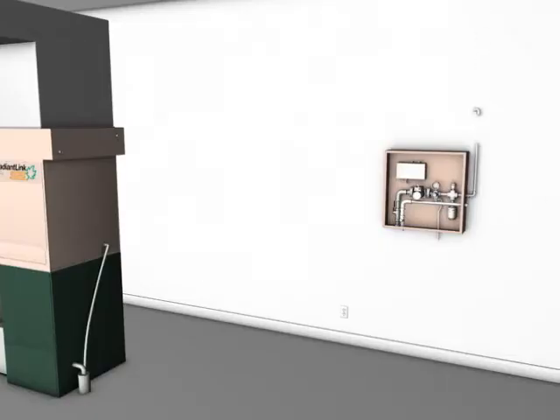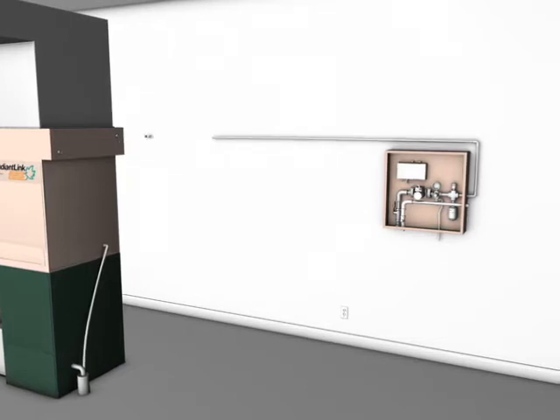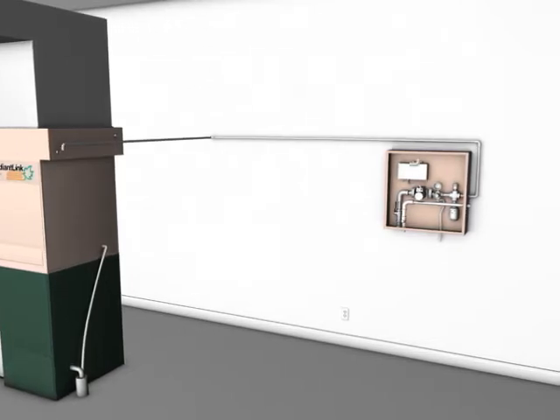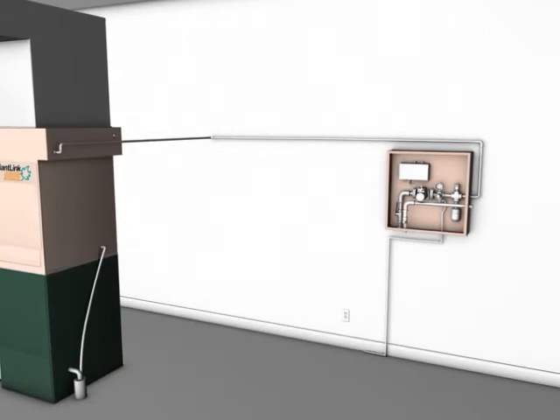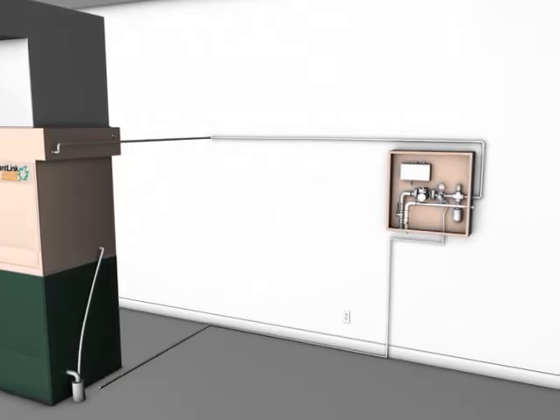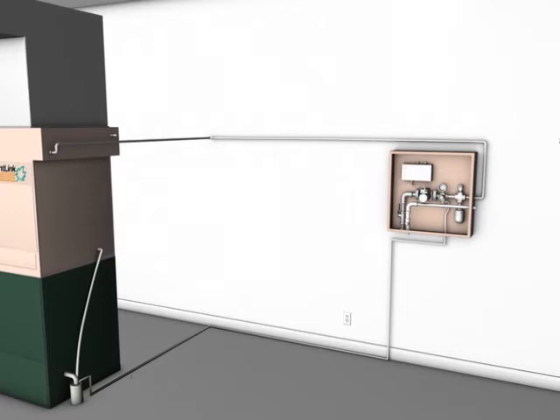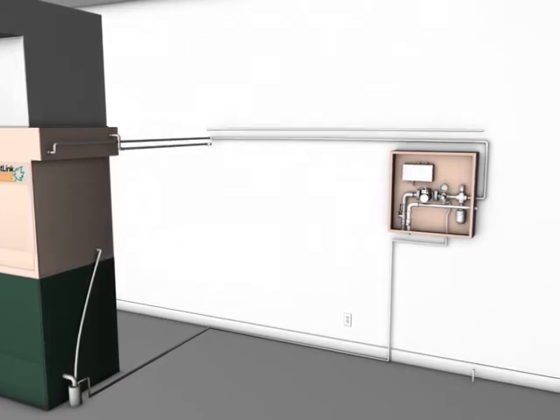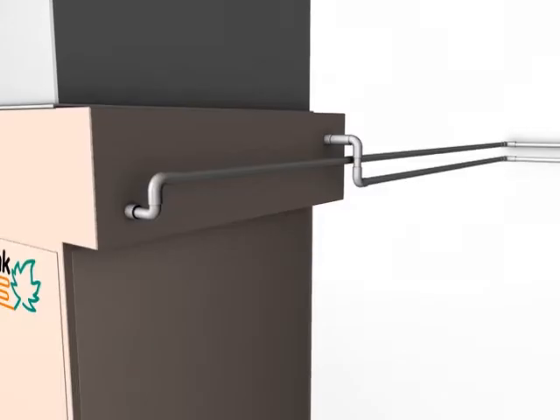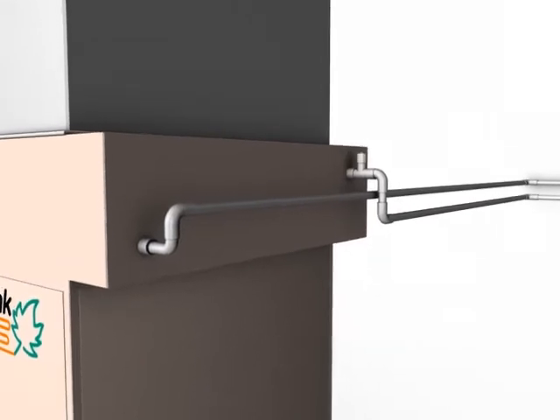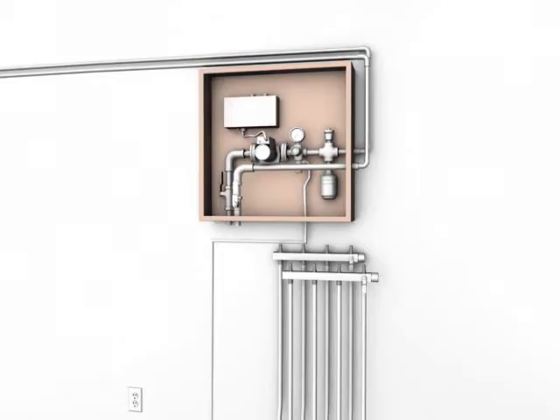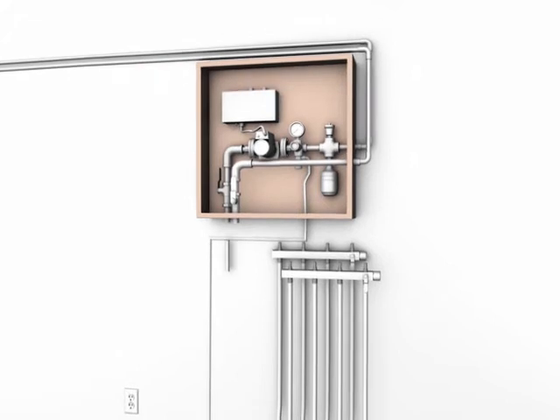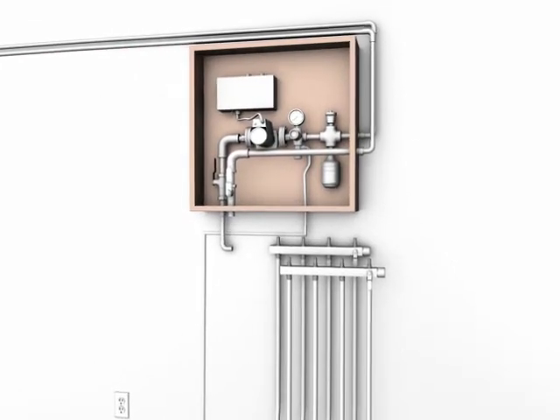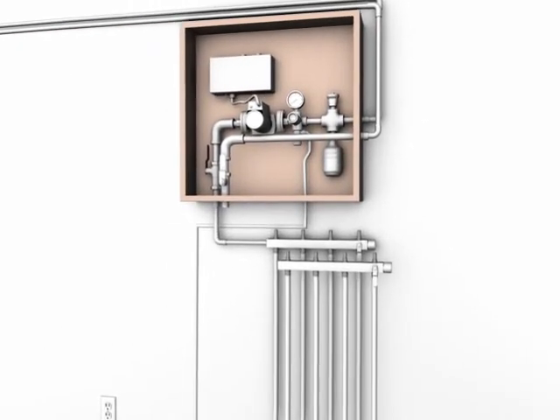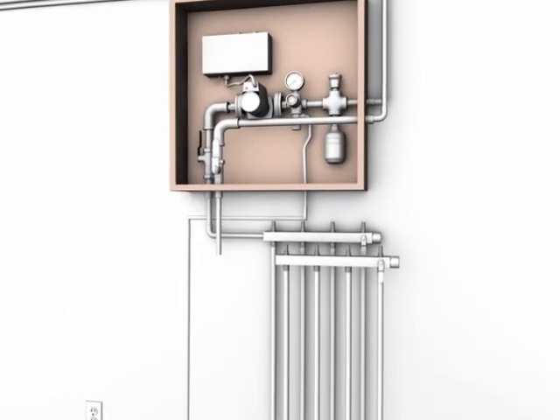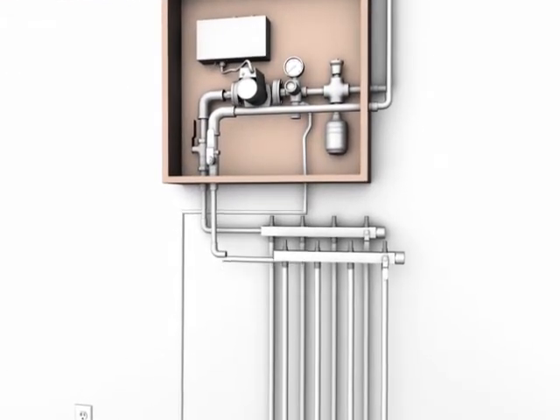Pipe the control panel discharge A on the control panel side to the plenum coil inlet connection B. Pipe the relief valve discharge in the control panel to a floor drain. Pipe the plenum coil discharge connection C to the control panel side inlet connection D. Provide an air vent at this location, or at the highest part of the system. Pipe the discharge E on the control panel bottom to the radiant floor supply manifold. Pipe the inlet F on the control panel bottom to the radiant floor return manifold.